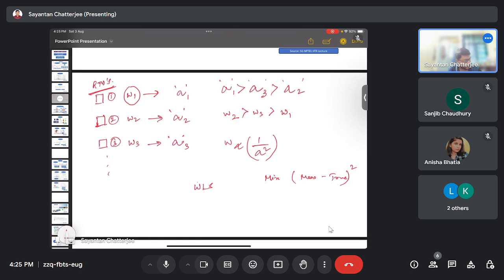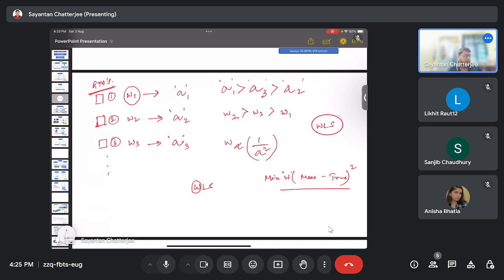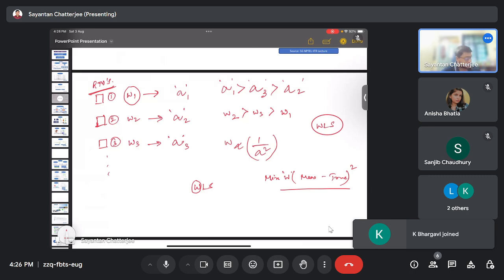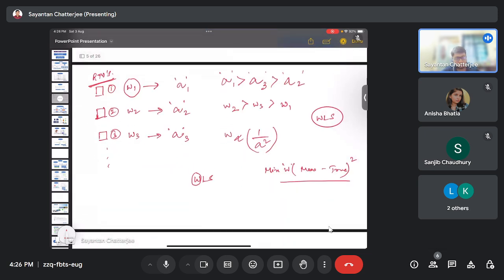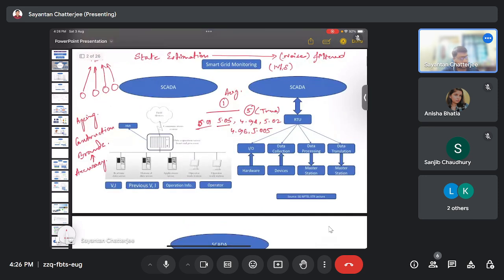Now, with the weights being prescribed for each and every instrument, the assumption of the problem becomes much more pertinent to the context of the power system. So W gets assigned, and along with that this becomes the weighted least square estimate. The basic state estimation, which we call weighted least square estimators, runs in the NLDCs, National Load Dispatch Centers, and these WLS estimators perform based on the data acquired from all these RTUs.